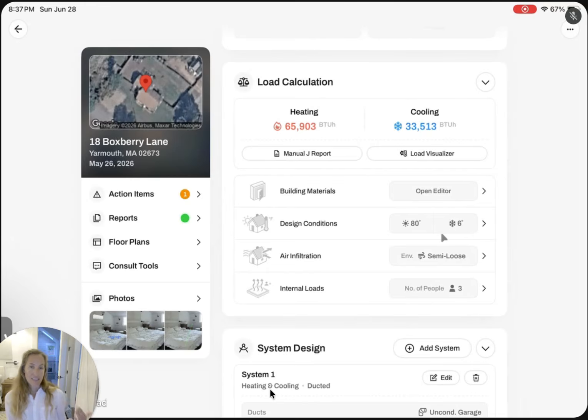In this case, I'd like to size a whole home ducted heat pump, and I'm going to size it to the cooling load. I'll plan to install backup heat. I can tell with this cooling load of 34,000 BTUs, we're looking at a 3-ton system. Where this feature comes in really handy is for those loads that are right on the line, between 2.5 tons and 3 tons, 3 tons and 3.5 tons.